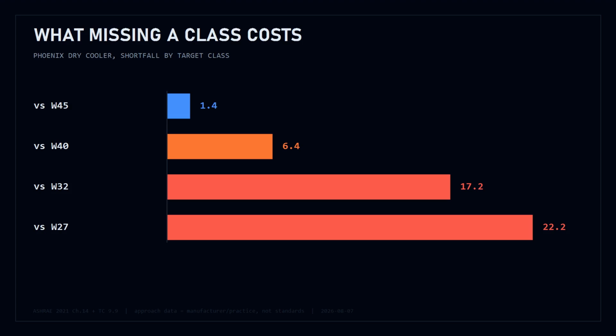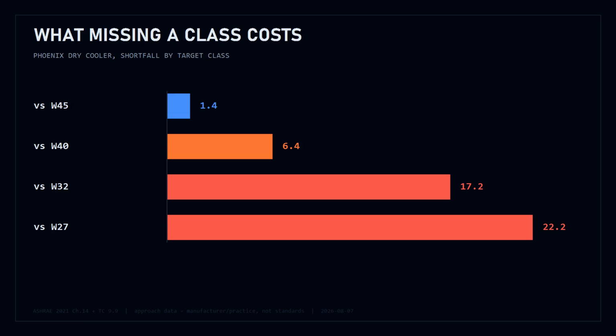What does missing a class actually cost? Not an outage, derating. You do not lose the site. You lose the top of its capacity during the hours the design condition is exceeded. And because that is a percentile of the whole year, those hours cluster in the hottest weeks, which is also when the grid is tightest and power costs the most. The penalty lands exactly where it hurts. Or you fit a chiller and pay for it in electricity for 20 years.